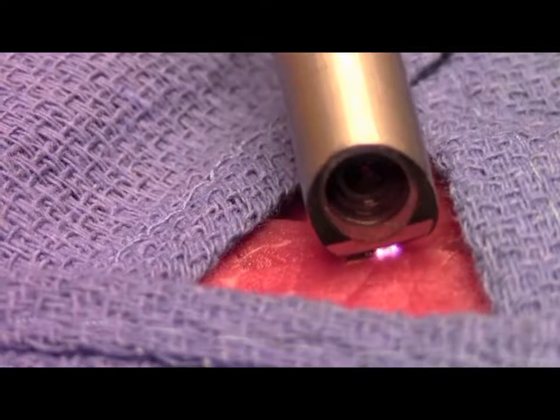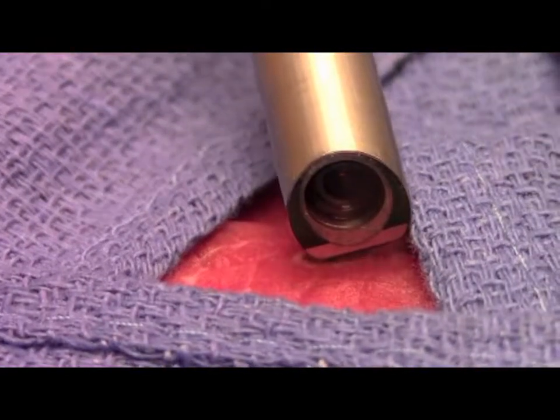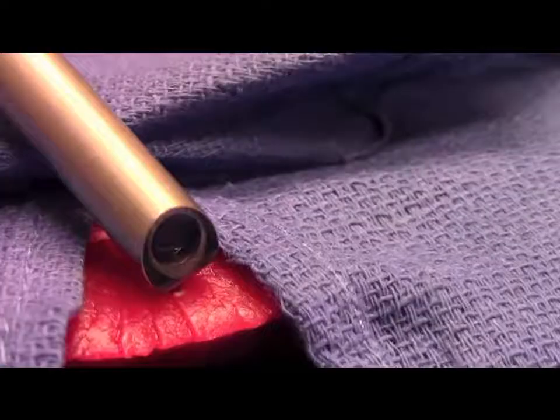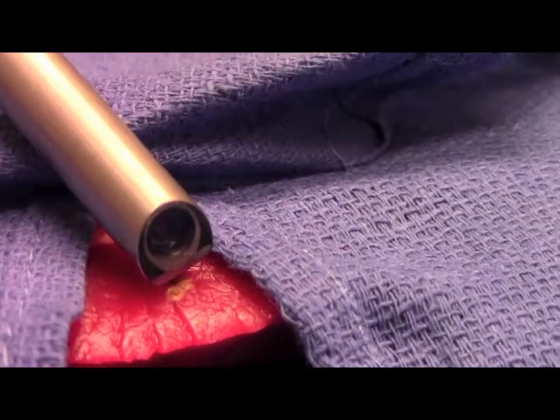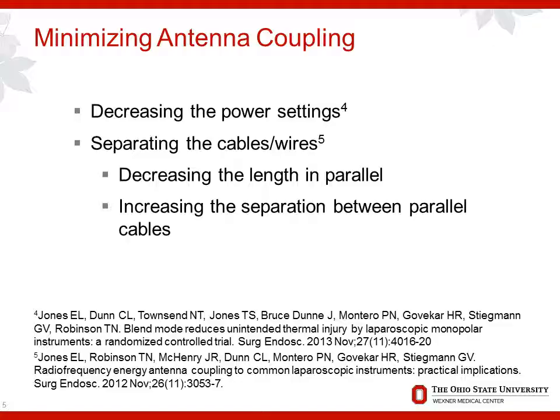As this video demonstrates, so much energy is transferred that we can see, smell, and even hear energy arcing from the telescope tip to the tissue. Subsequent studies have further defined practical steps that can be taken to minimize the coupling of energy. This includes decreasing the energy used by reducing the power setting or selecting a lower energy mode, such as cut or blend mode, in contrast to the standard coag mode. In addition, separating the active electrode or Bovie cord from other cables has been shown to reduce the incidence of burns in a randomized controlled trial.